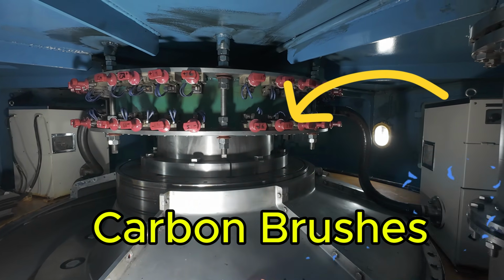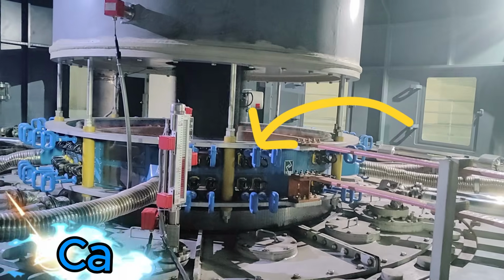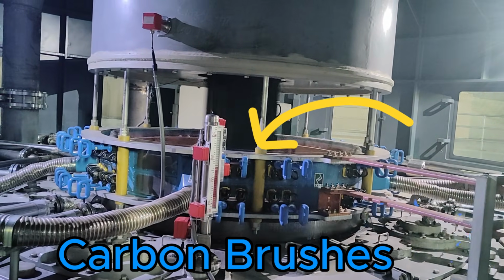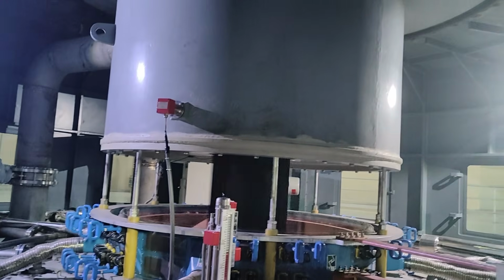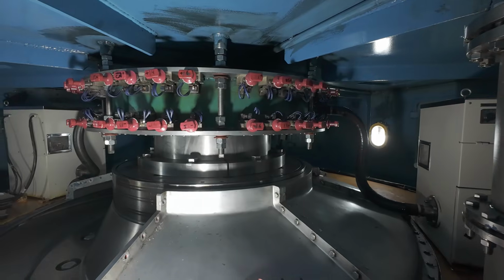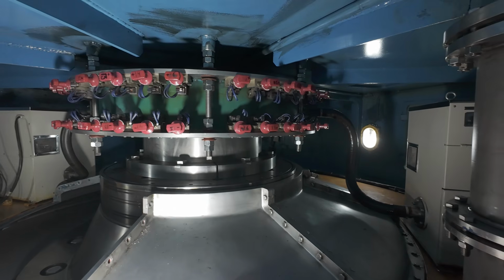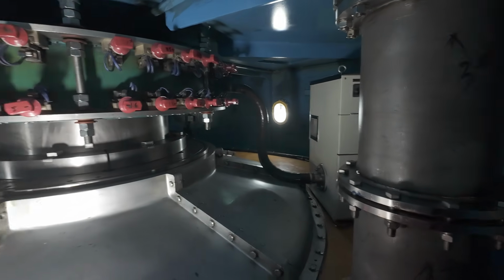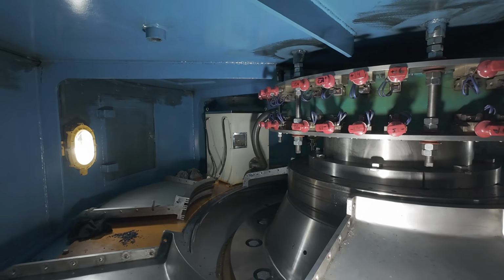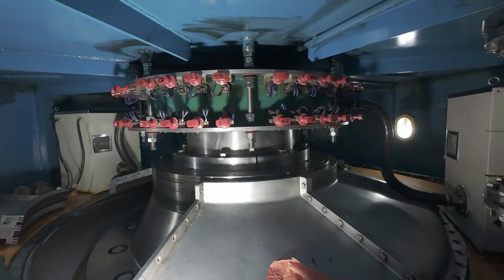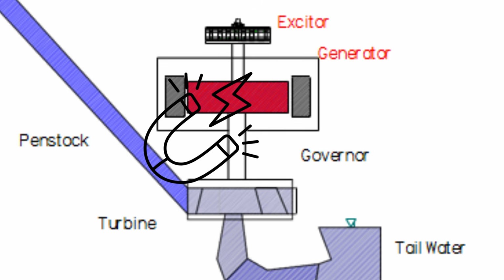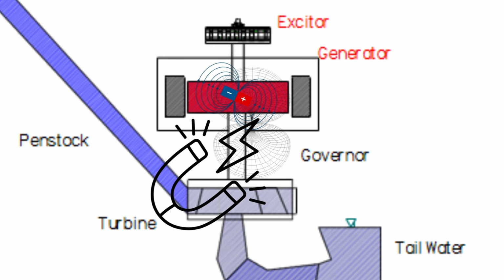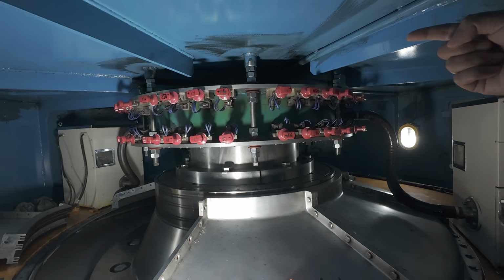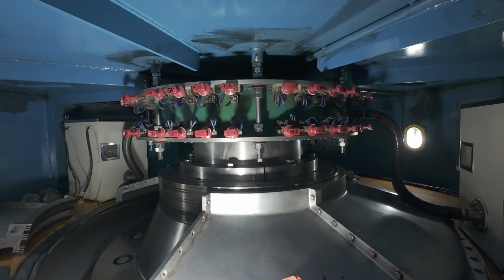So the carbon brushes stay fixed while the rings spin continuously. This creates a moving electrical connection between the stationary excitation system and the rotating rotor. So DC current flows through the carbon brushes into the exciter ring and finally into the rotor winding itself. That current transforms the rotor into a giant electromagnet. And once that magnetic field starts rotating inside the stator, the generator finally comes alive. Without excitation, there is no magnetic field. Without a magnetic field, there is no power generation.